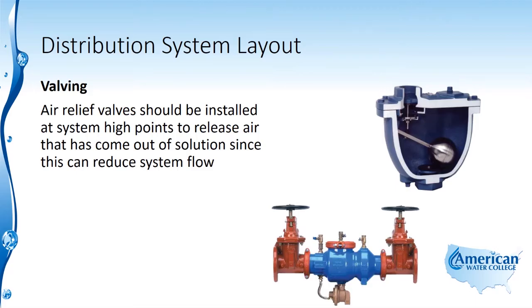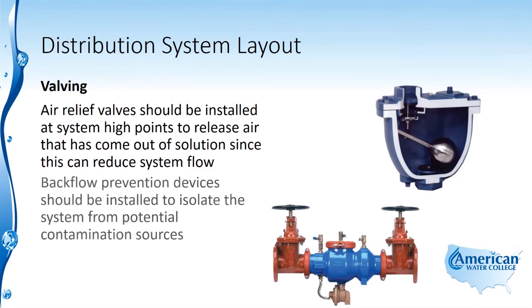Air relief valves should be installed at the system high points to release air that has come out of solution, since this can reduce system flow. Backflow prevention devices should be installed to isolate the system from potential contamination sources.